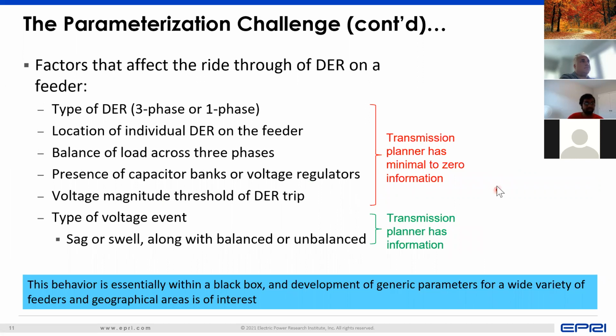It also goes about with respect to the type of DER, the type of load, the presence of capacitor banks, the type of voltage event, because all of this plays a role in how the DER can behave during an event that occurs on the transmission system. And actually, out of these 6 categories that are here, a transmission planner has minimal to zero information on 5 of them, because they are all well within the distribution system, into which the transmission planner may not have visibility. And the transmission planner may only have information on the type of voltage event that has occurred on the transmission side. So essentially, we have a black box distribution system model, and we are trying to identify how that model will behave despite these various uncertainties. Can we really understand how that model will behave so that when I'm doing a transmission planning study, I can make a reasonable enough judgment for the behavior of my system?